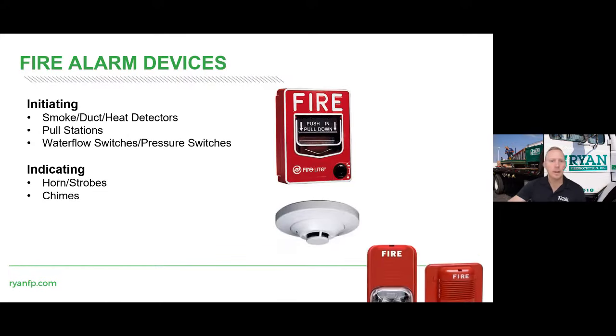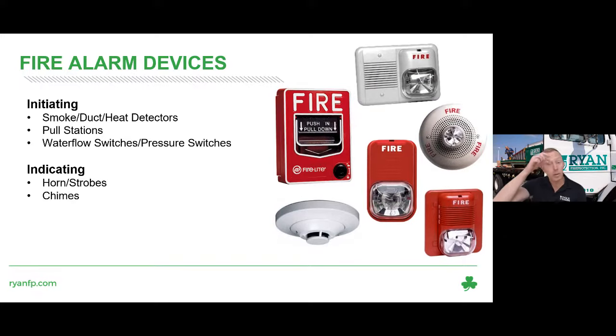Next we want to talk about fire alarm devices. As I mentioned earlier, there are two main categories: initiating and indicating. It can be a tongue twister if you say it too fast, but initiating devices are devices that initiate an alarm, trouble, or some sort of signal. Examples include smoke detectors, duct detectors, and heat detectors. They send a signal to the fire alarm control panel, putting the system into trouble and getting you a phone call to let you know something's wrong, or putting it into alarm, which brings fire trucks to assist with your emergency.